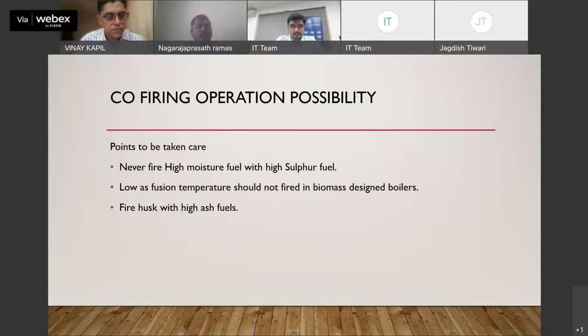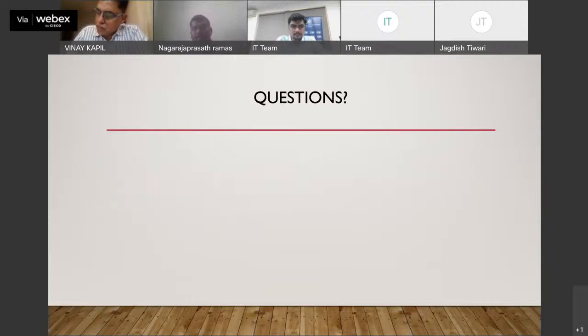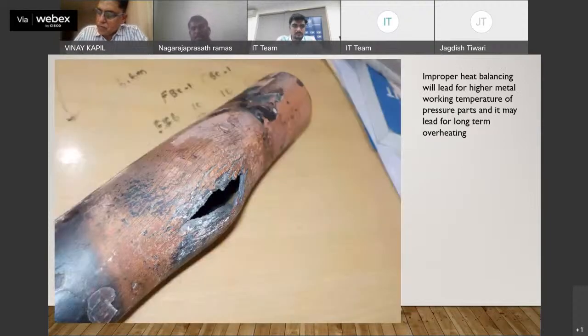If you want to use a low fusion temperature fuel, definitely you need to add more evaporator panels so that the superheater gas temperature will be in control. And one more thing: high ash fuels along with biomass are much better, because high ash fuels capture the moisture available in the biomass, so that corrosion and fouling problems will become less. That's all, sir.